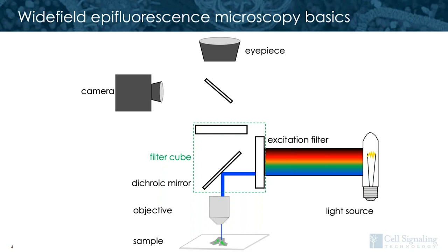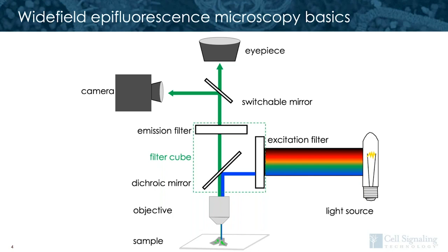This light is directed through the emission filter to a switchable mirror. From here, light can be directed to the eyepiece or to a camera. While imaging on an epifluorescent microscope is speedy, you're working with all of the light collected from the sample. There aren't many features here to eliminate out-of-focus light. And the filter sets are broad enough that some background and autofluorescence will likely be imaged if it exists in your sample.